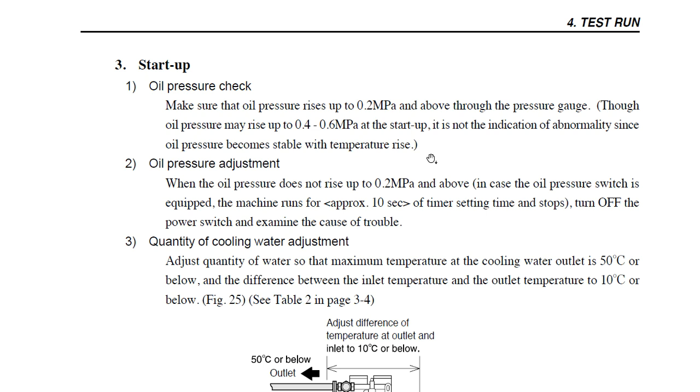If for any reason the oil rises to 0.4 or 0.6 megapascals on startup, maybe this is not an indication of abnormality. We need first of all to stabilize the temperature of oil as the compressor is working. When the temperature increases, the oil pressure decreases due to the change of viscosity.